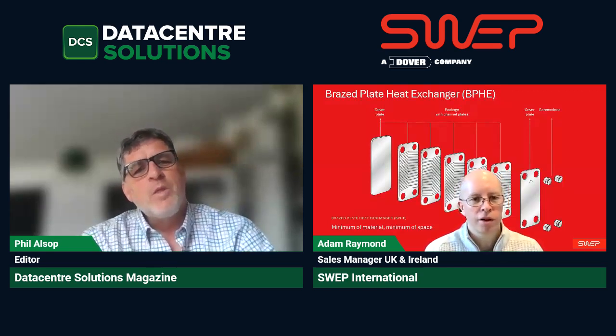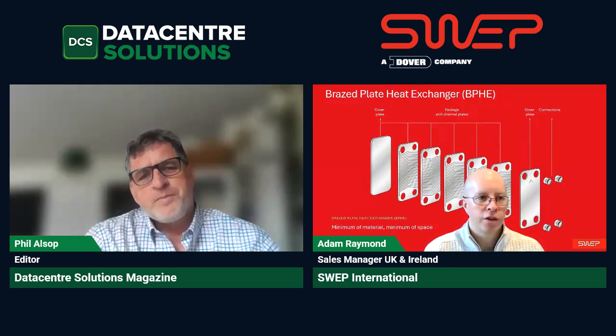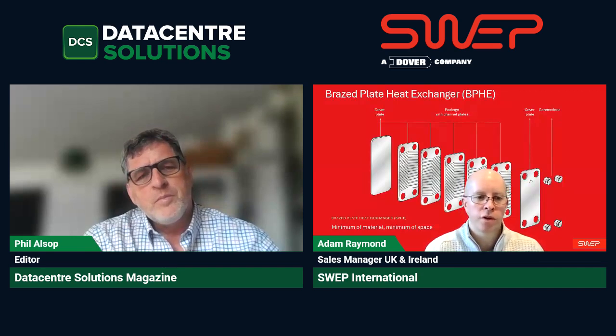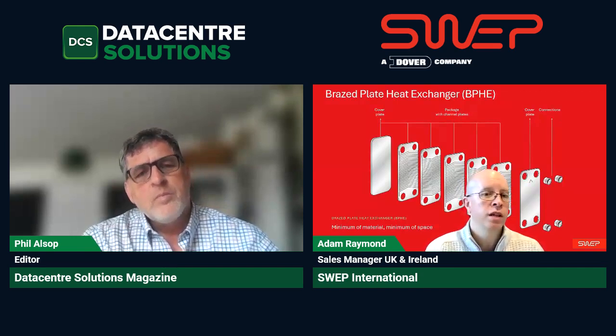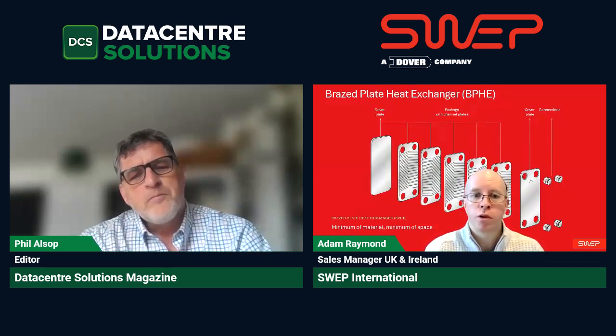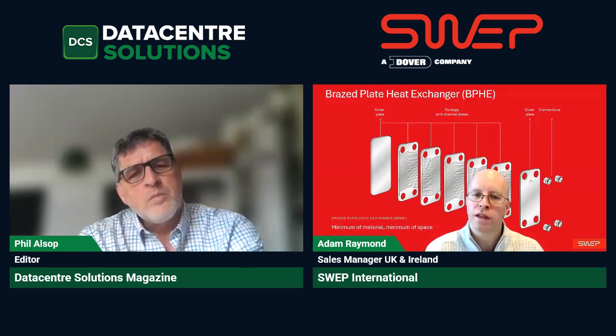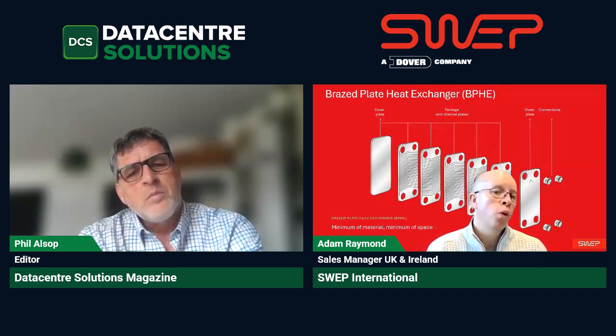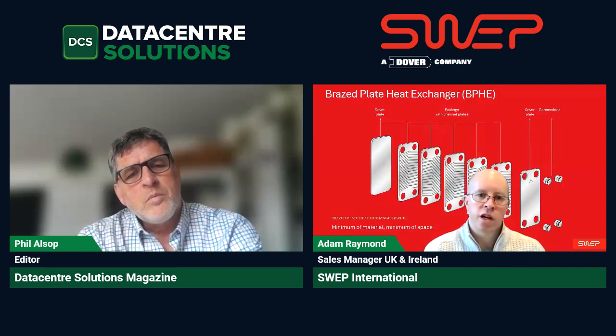Yeah, absolutely. So heat recovery is another hot topic, and it almost connects us with another industry we're a lot more familiar with, which is district energy. This would be the typical consumer of waste heat, and ideally the data center is located next to a network. Broadly speaking, there's two ways we can recover heat from a data center. We can take it directly from the liquid, the water that's cooling the server racks, be that direct to chip or rear door heat exchanger. So as that warm water is coming back from the server racks, we're basically intercepting that with a heat exchanger and sending it off somewhere, ideally again district energy.